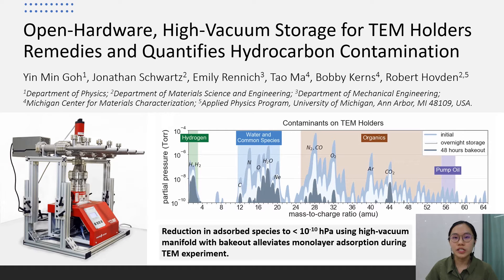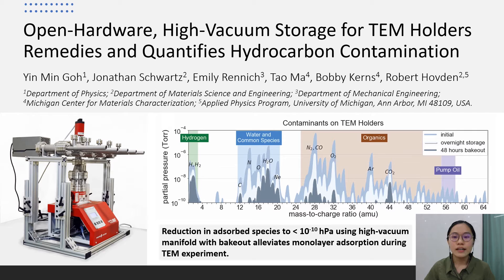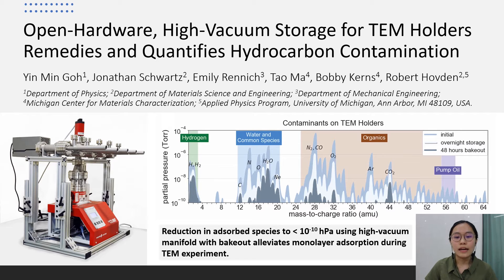Here on the right is a residual gas mass spectrum of a TEM holder commonly stored in a desiccated cabinet. We have carried out similar measurements on several other holders, and they all show that TEM holders are inherently dirty and introduce a range of unwanted species into vacuum. So, we have come up with a high vacuum storage solution that also includes a bake-out system. In this talk, I will show you how this manifold can offer up to four orders of magnitude reduction in adsorbed species on a TEM holder, and helps to alleviate monolayer adsorption during TEM experiments.